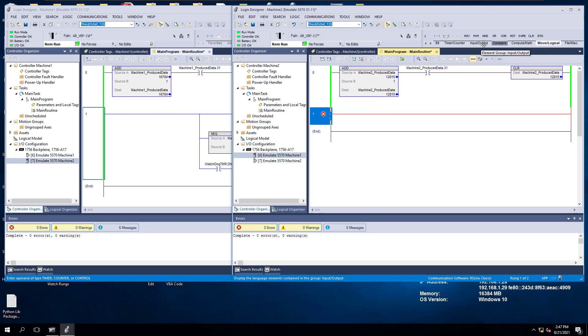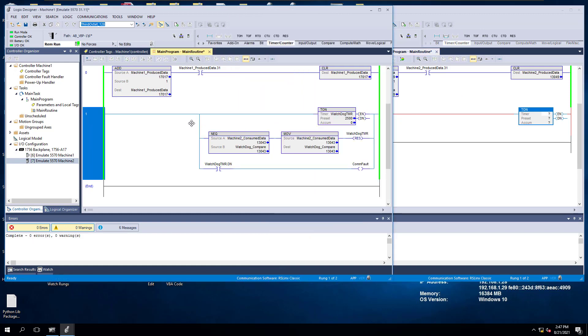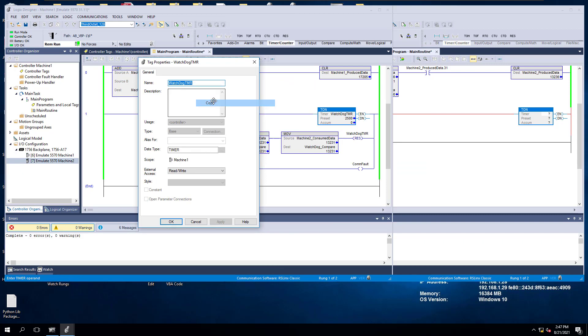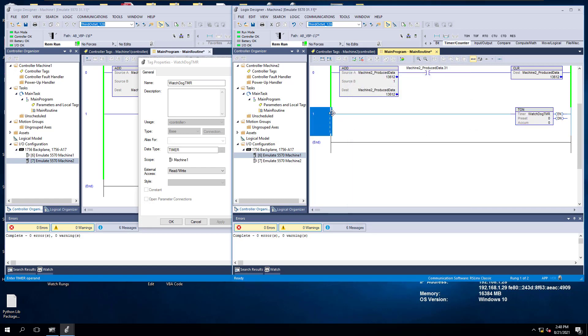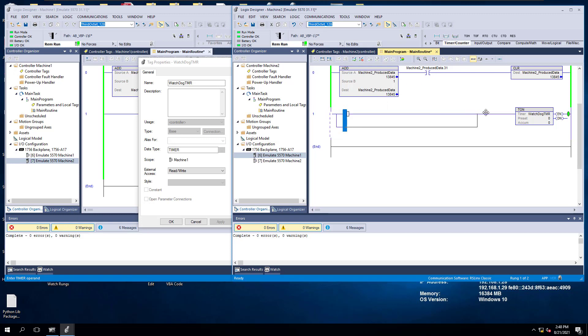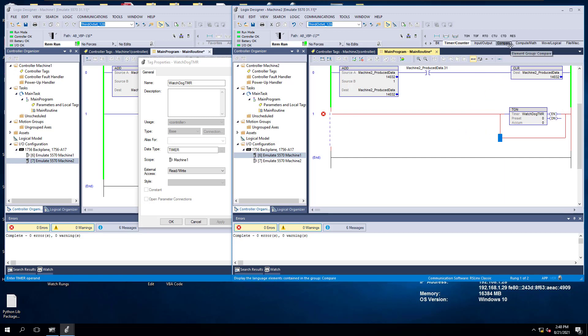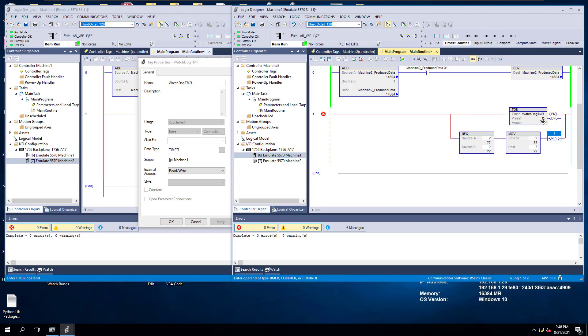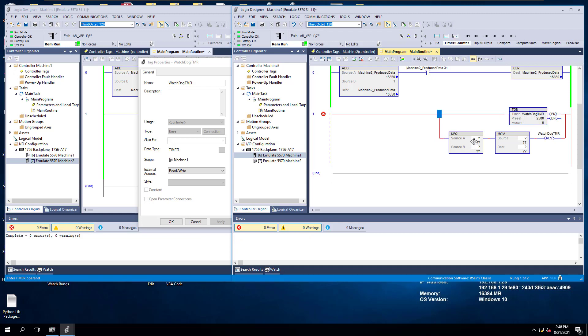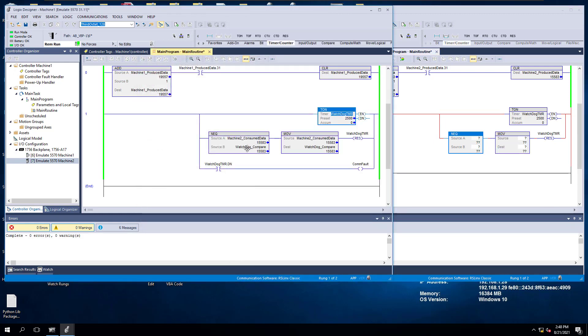Let's go ahead and do another timer — this is machine two. We're going to do the exact same thing in machine two. We can really call it the same thing if we want to, because it's in a different processor. Watchdog Timer — this keeps what you're doing in one and what you're doing in the other consistent, and it keeps it easy to read for somebody coming behind you. Every watchdog is done differently, so please understand I'm showing you one instance. We're basically going to say if it's not equal to, then we're going to move that data into that data, and then clear that data. Instead of using a clear, we're going to use a reset for the timer — that's how you would do a timer. We'll put a value of two and a half seconds.